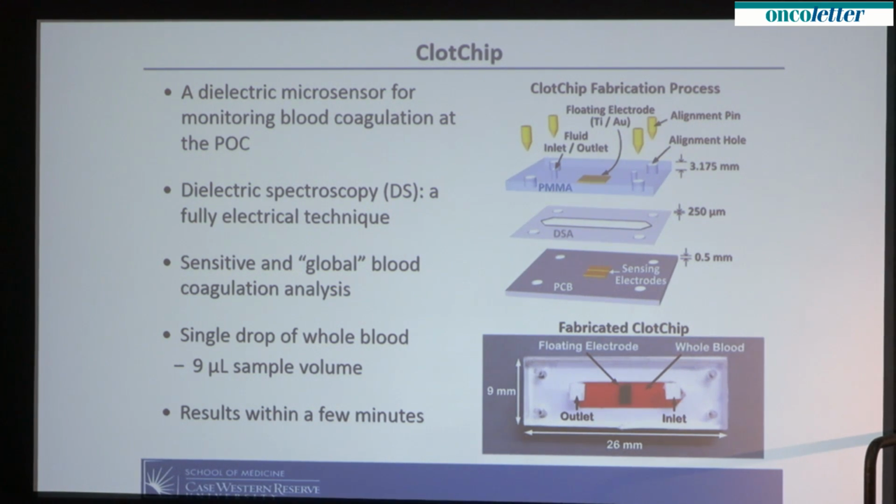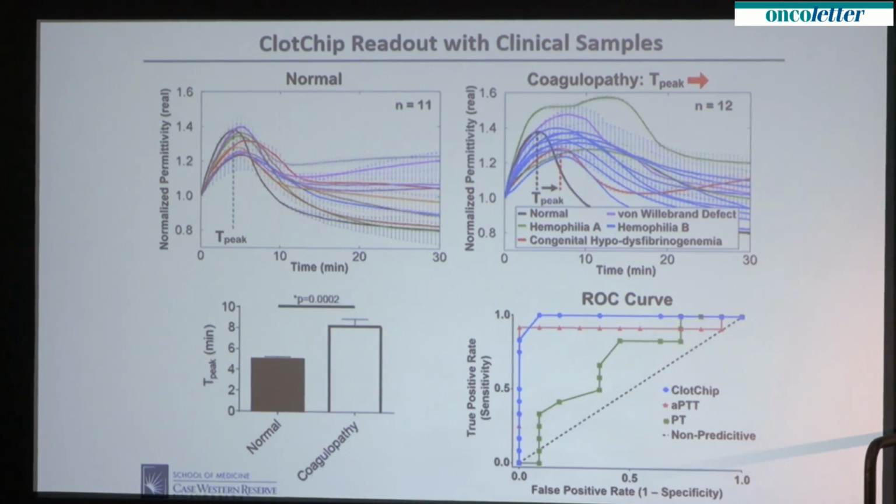The prototype ClotChip sensor is shown here, and it features a parallel plate capacitive sensing structure with a floating electrode that extracts the dielectric permittivity of blood in a microfluidic chamber. As a blood sample flows through the area, the impedance of the sensor changes depending on the permittivity of the blood sample.